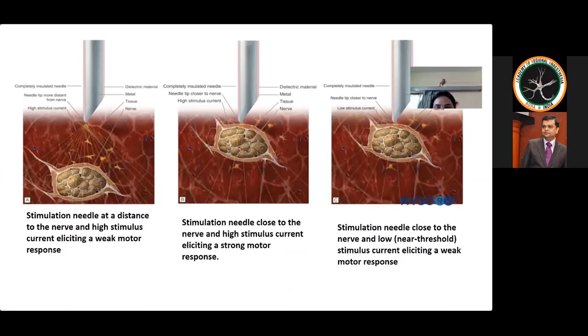Now coming on to the impedance or the complex resistance. So it is the resistance of the nerve stimulator, needle, tissue characteristic of the patient, and the grounding electrodes and the cables. Now this impedance will depend upon the frequency content of the stimulus. Now the major impact is mainly formed by the needle tip and the electrode in the skin impedance.